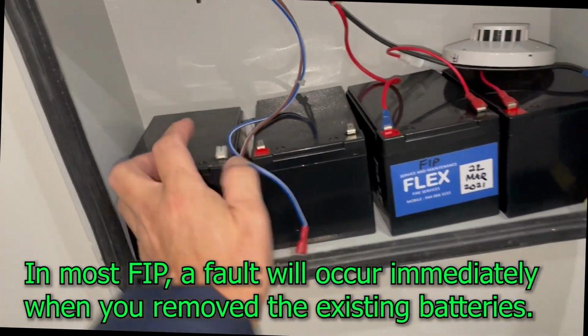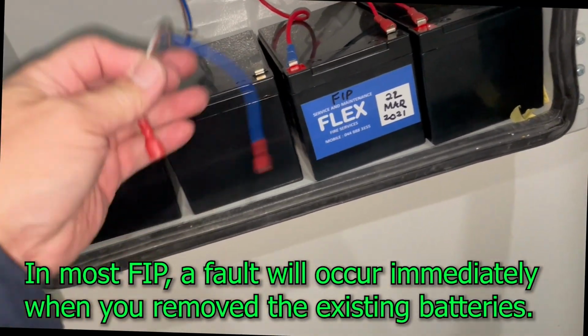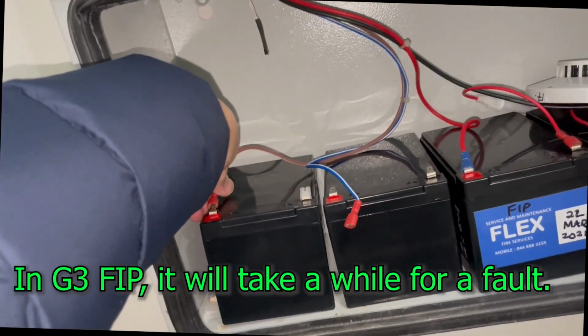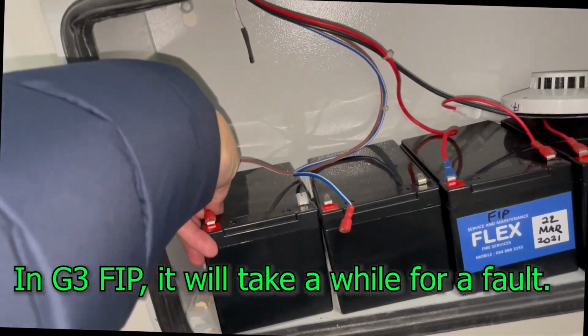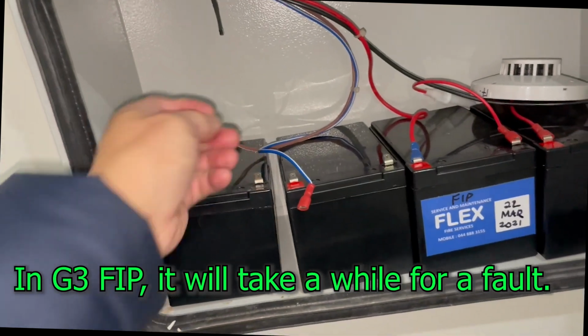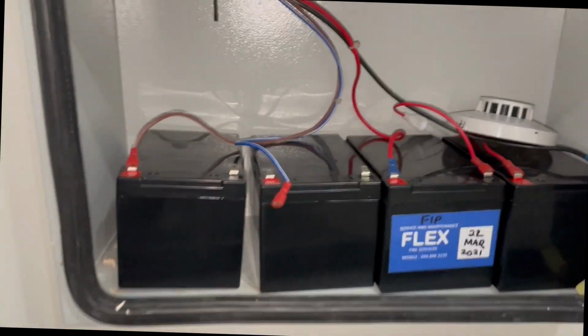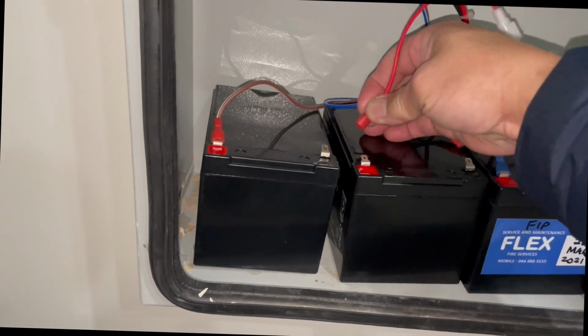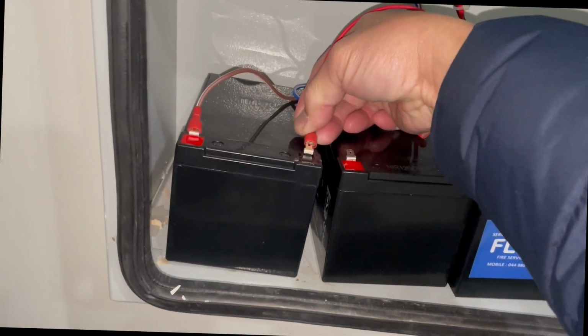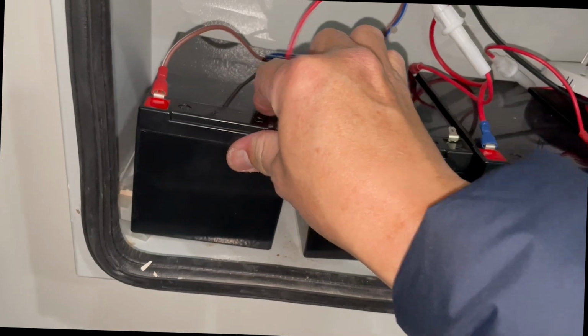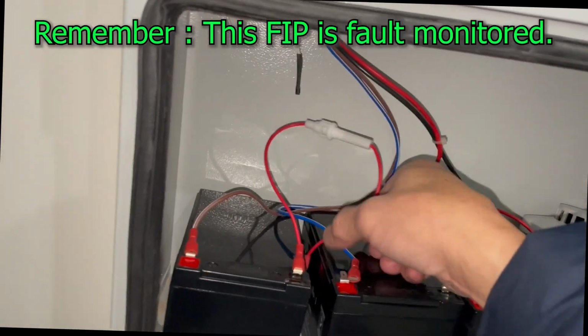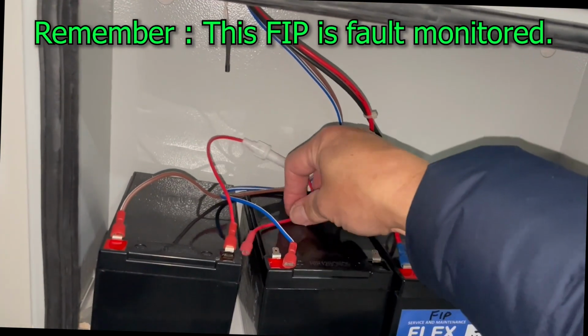See, what I found out is that it takes a while before the fire alarm panel gets the fault for battery removal. So I said, oh, that's good, so I can do my job without any fault in the system. So I don't need to isolate the alarm signaling equipment. All I need to do is just change the battery.